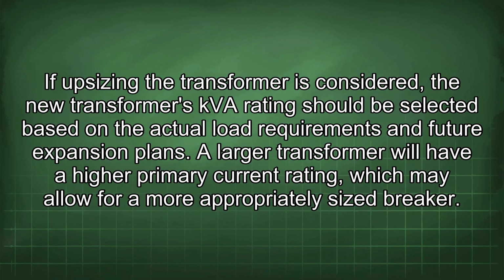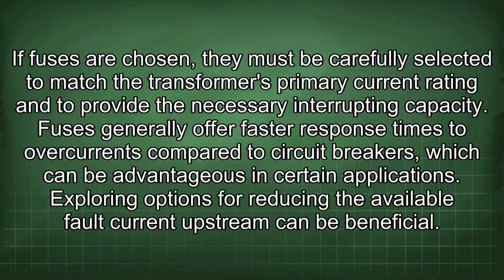If upsizing the transformer is considered, the new transformer's kVA rating should be selected based on the actual load requirements and future expansion plans. A larger transformer will have a higher primary current rating, which may allow for a more appropriately sized breaker. If fuses are chosen, they must be carefully selected to match the transformer's primary current rating and to provide the necessary interrupting capacity. Fuses generally offer faster response times to overcurrents compared to circuit breakers, which can be advantageous in certain applications.